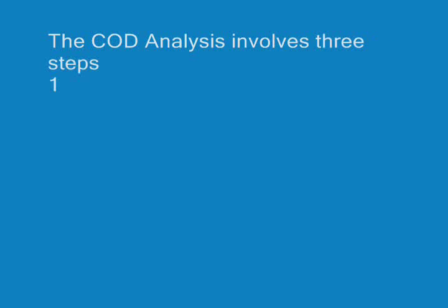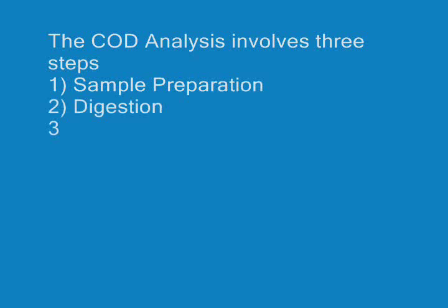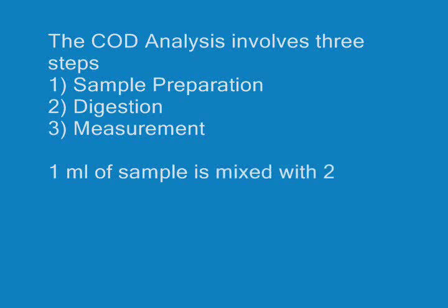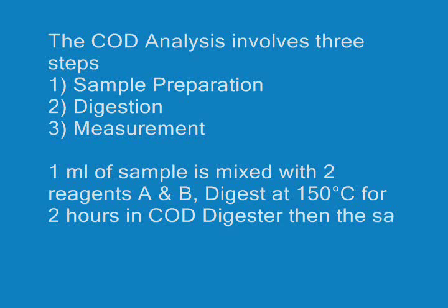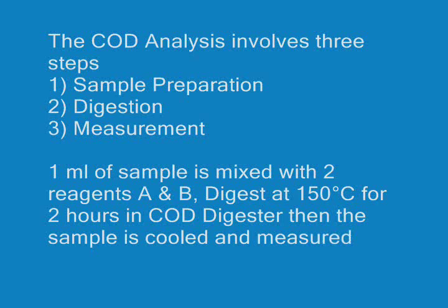The COD analysis involves three steps: first, sample preparation; second, digestion; third, measurement. One ml of sample is mixed with two reagents, A and B, and digested at 150 degrees Celsius for two hours in a COD digester. Then the sample is cooled and measured on the COD analyzer.